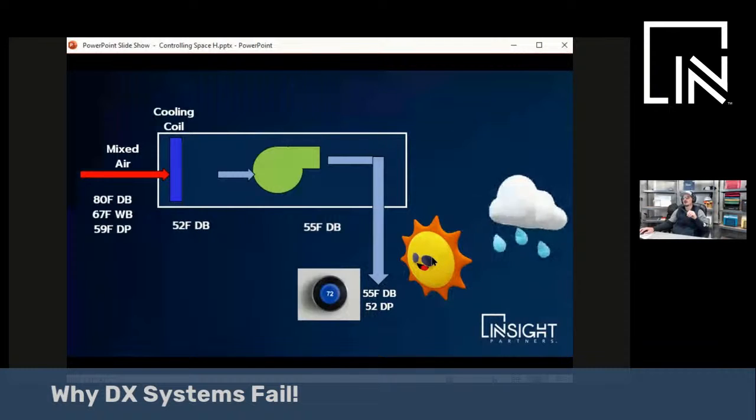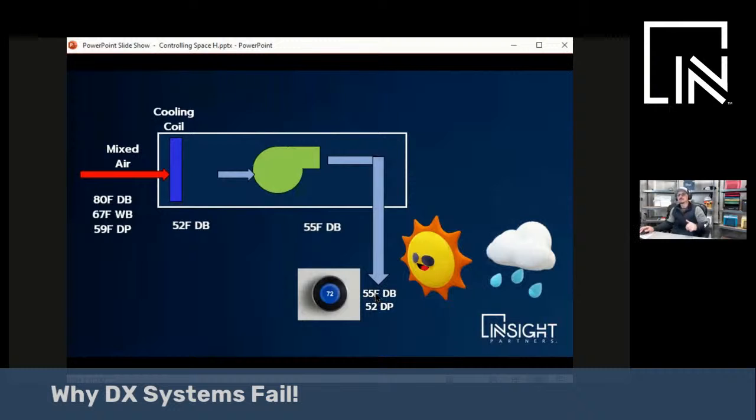What happens is, on a part-load day, it's October, November, it's cool and rainy, it might be 65, 70 degrees. This 55-degree air will make it very cold in the space. So what happens is the system will cycle back the cooling. It'll either turn off the compressors, or it'll turn down the compressors and elevate this leaving air temperature.